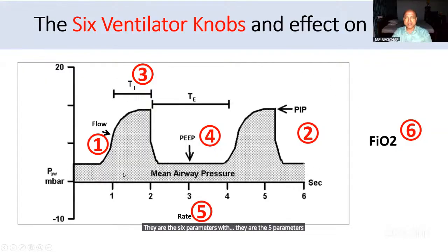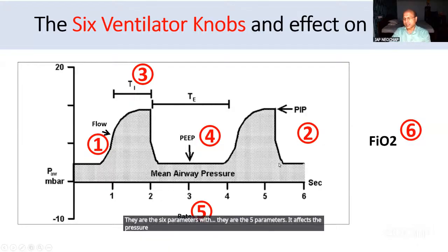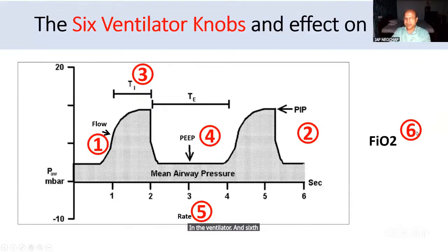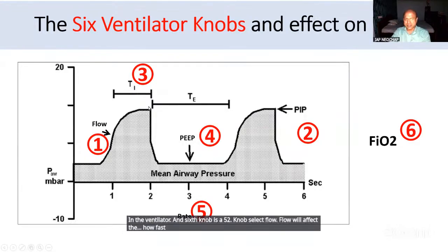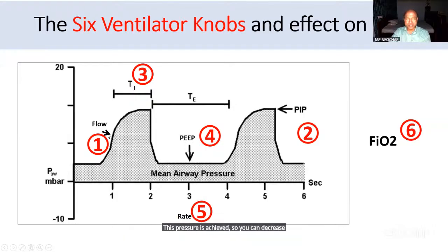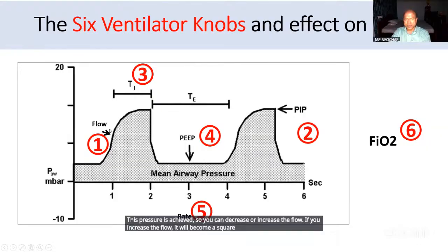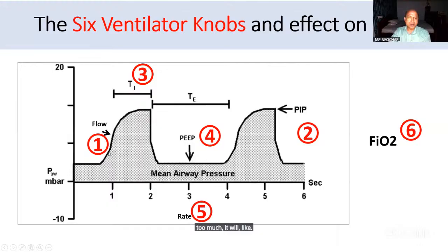There are 5 parameters which affect the pressure waveform in the ventilator, and 6 knobs. The first is flow. Flow will affect how fast this pressure is achieved. So you can decrease or increase the flow. If you increase the flow, it will become a square one, and if you decrease the flow too much, it will become almost sinusoidal. Then it will become V-shaped like this. And there is a TI. TI means how much inspiratory time we are giving, so how much time the increased pressure is there. Then you have PIP, how much pressure maximum we are giving. And rate also. So there are 6 knobs you have to operate.